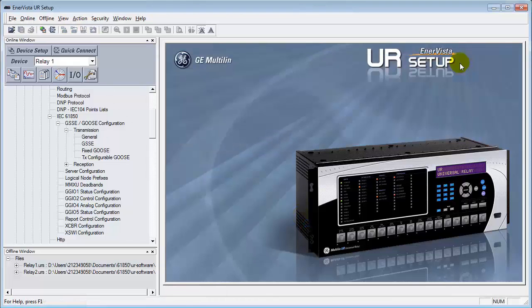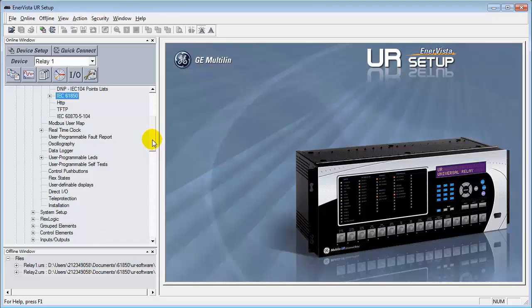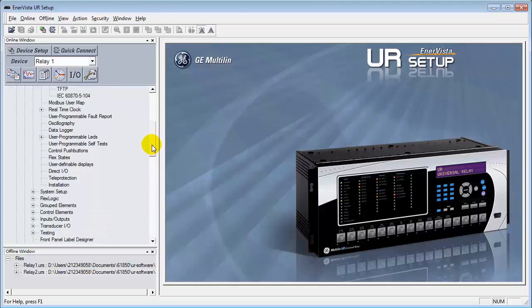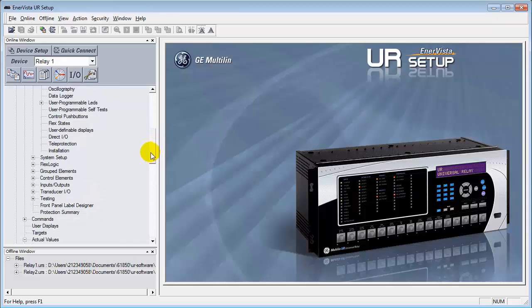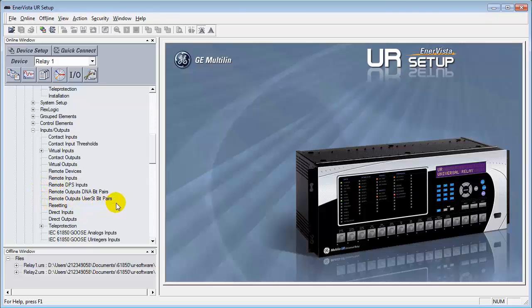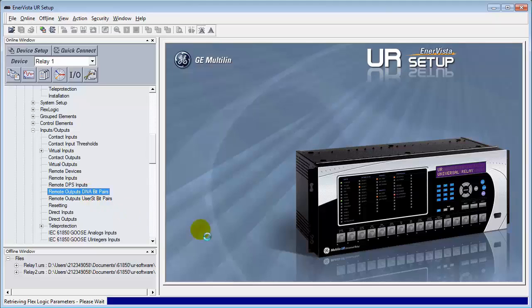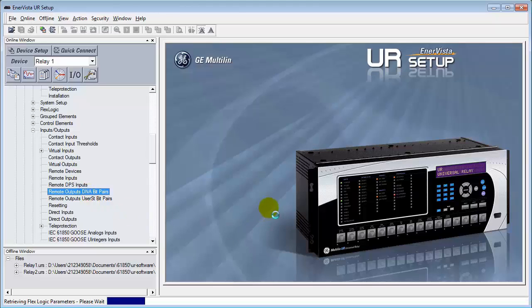Now, on the fixed goose, we have to go down to the inputs and outputs section to basically publish the signals that we're going to be transmitting across the network. So under inputs and outputs, let's expand this here. Come down to contact inputs and outputs. And what we're going to do is we're going to focus on this area here, the remote outputs. Because these are our bit pairs that we use for fixed goose messaging. So let's start off first with this, the DNA bit pairs. There's 32 bit pairs. And in here is going to determine what the signals are that we're going to publish.